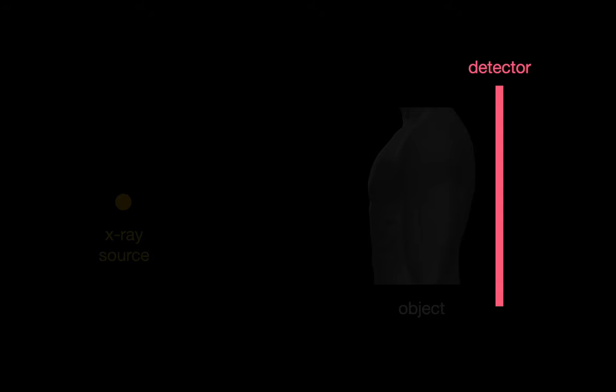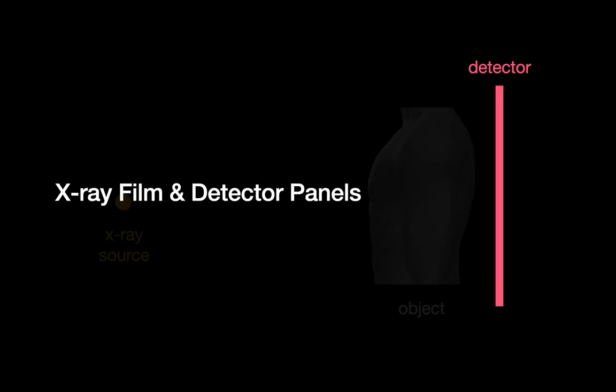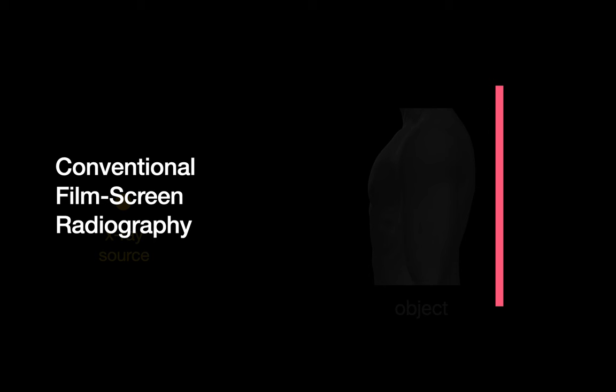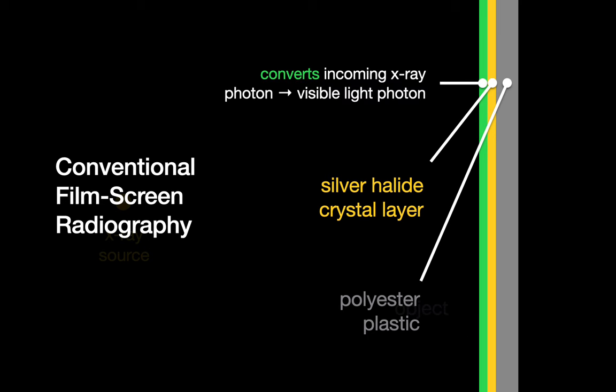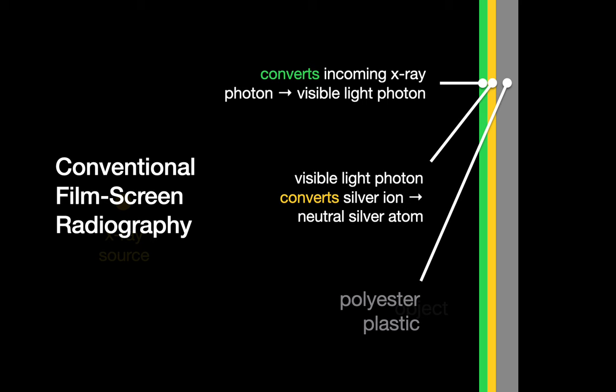Now, let's take a close look at the x-ray film or detector panel that captures our portable chest x-ray image. There are three strategies for doing this, and one of them has been in use since the late 19th century: conventional film screen radiography. With conventional film screen radiography, we capture a patient's chest x-ray image using a sheet of plastic that's coated with a layer of light-sensitive silver halide crystals and then coated with a layer of phosphorescent crystals. Whenever an x-ray photon hits the phosphorescent crystal layer, the phosphorescent crystal at that spot converts the x-ray photon into a photon of visible light. The visible light photon then converts an adjacent silver ion within the silver halide layer into a neutral silver atom.